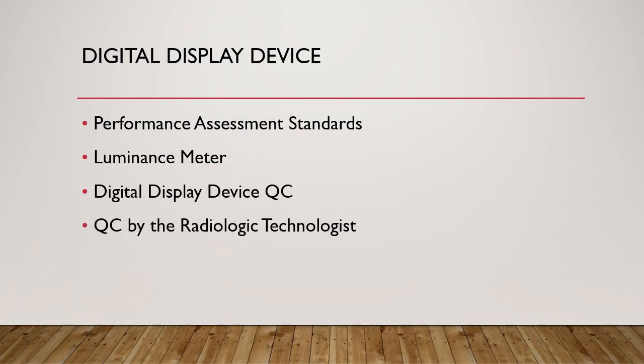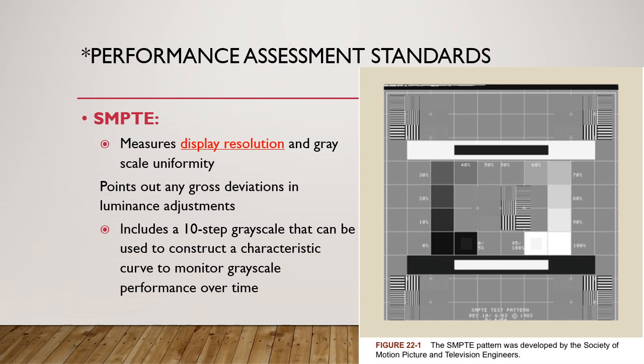So now we have digital display device items to look at. Performance assessment standards: luminance meter, the digital display device for QC, and the QC by the radiologic technologist. The SMPTE pattern is going to measure display resolution and grayscale uniformity. It points out any gross deviations in luminance adjustments and involves a 10-step grayscale that can be used to construct a characteristic curve to monitor grayscale performance over time. It was developed by the Society of Motion Picture and Television Engineers.